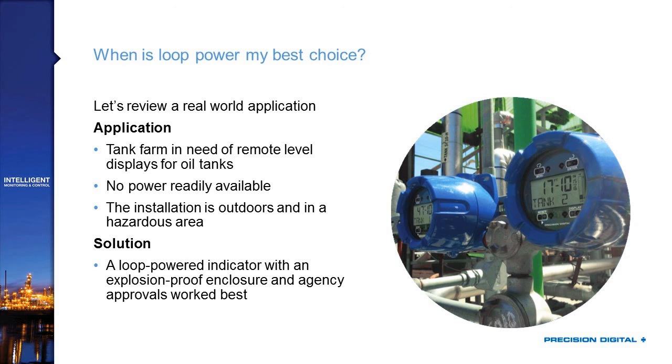Now they have a location where you can see both tanks clearly labeled in feet and inches on the ground with very minimal disruption to the plant due to the installation. So that's a great example of where you might see explosion-proof devices that are loop-powered being valuable, both because they're explosion-proof, and that's what the plant standardized on, but the loop-powered nature of it makes it a great choice for this easy installation.